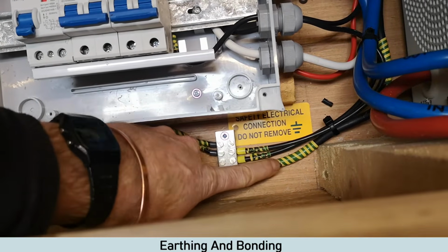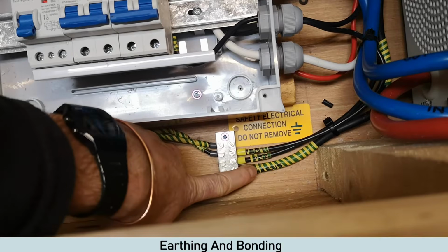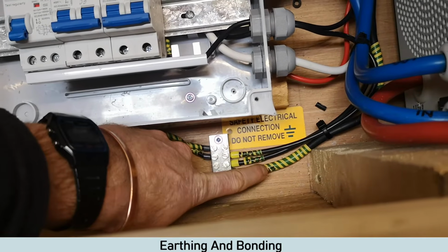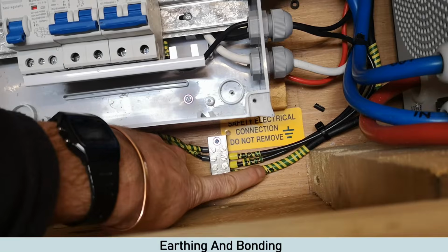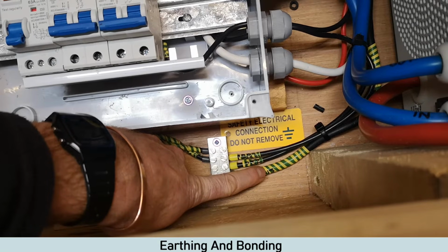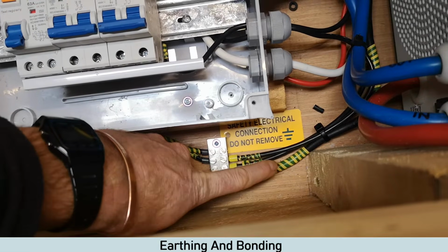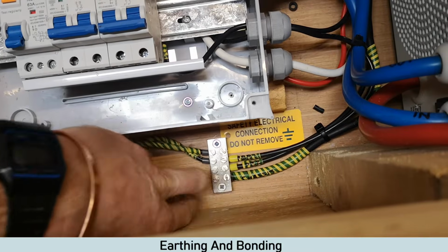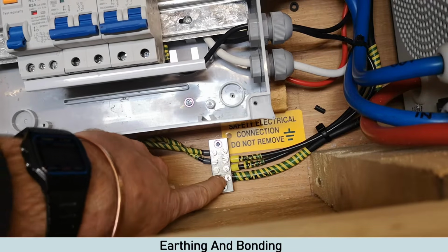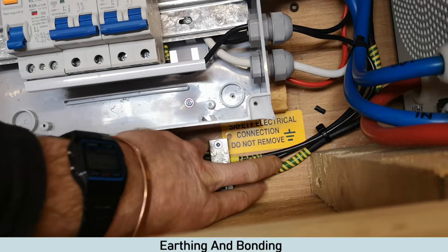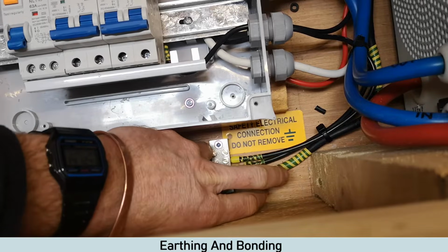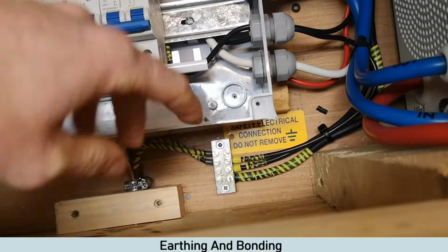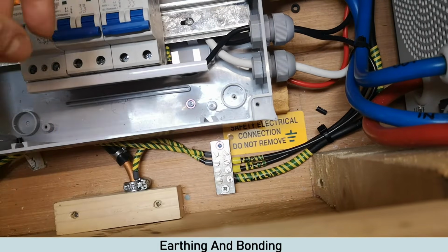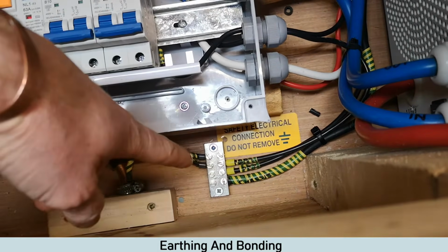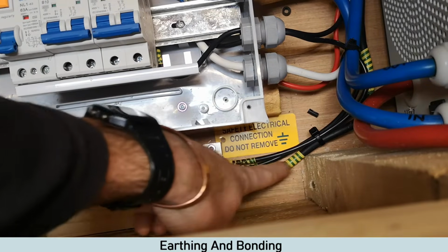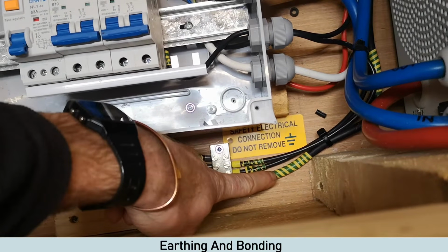So this beastie here goes straight onto our chassis. Now in the regs it does state that anything bigger than 4mm would be fine in a van. The reason we've used 16mm is because it's the biggest cable that will fit into here. We had some left over as well. Also, earthing acts as a fault path for fault current. The bigger the cable, the less resistance. So we thought whack a beast in and then there's no worries, is there?